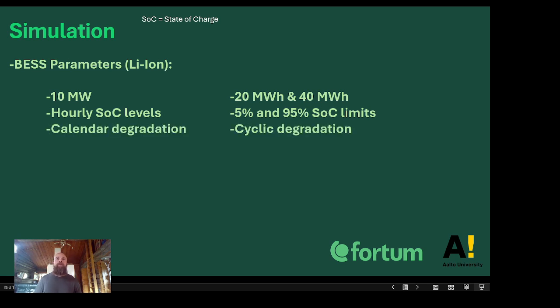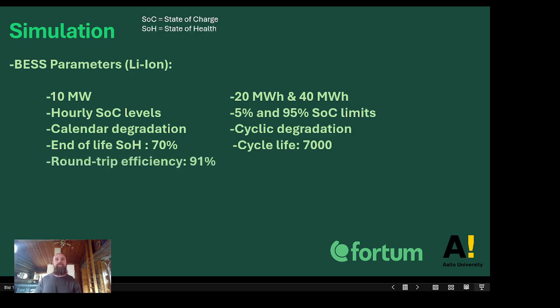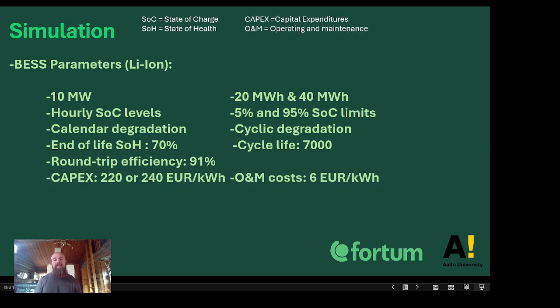I have modeled both calendar and cyclic degradation, and end of life state of health is at 70%, meaning how much the battery can degrade before reaching its end of life. Cycle life, how many cycles it can do before reaching end of life, is 7,000 cycles. Round trip efficiency is 91%, capital expenditures are 220 or 240 euros per kilowatt hour depending on the energy capacity, and operating and maintenance costs are 6 euros per kilowatt hour.